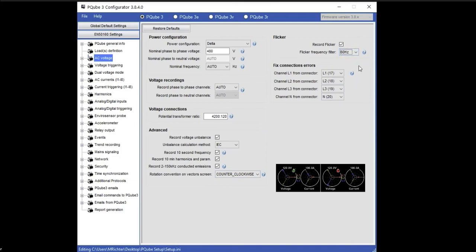If you have a missed wire and you've realized after you've connected the PQube that L2 is really L1 and L1 is L2, you can go and rewire the PQube, which is what I would recommend, or you can switch them around here. This physically changes the connections of the PQube for you inside the PQube. I'm going to leave them as they were. The PQube is now set up and ready to run. If you put this installation file on your PQube, it will measure and trend voltages for you.